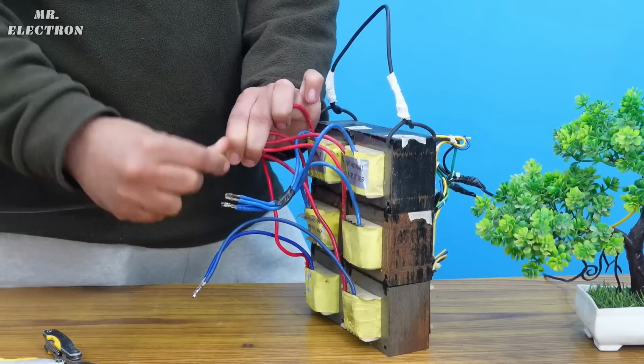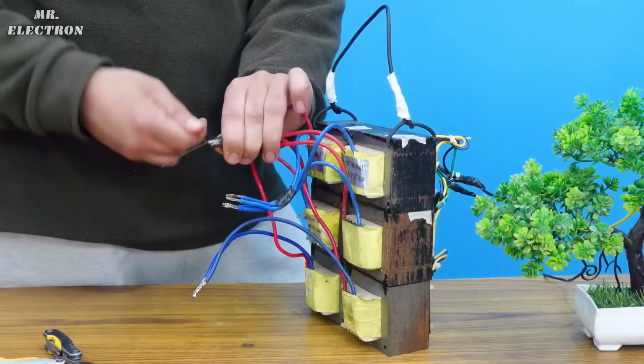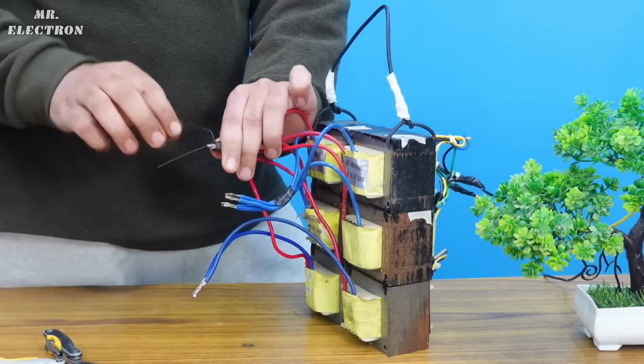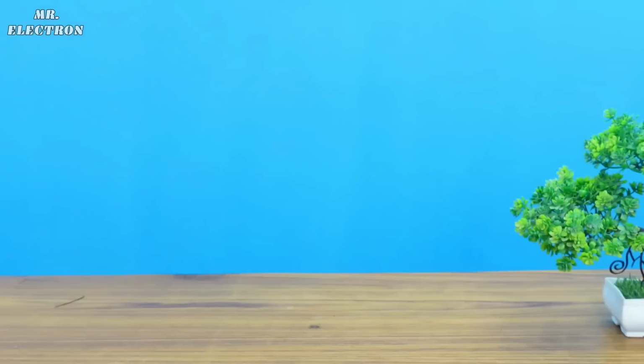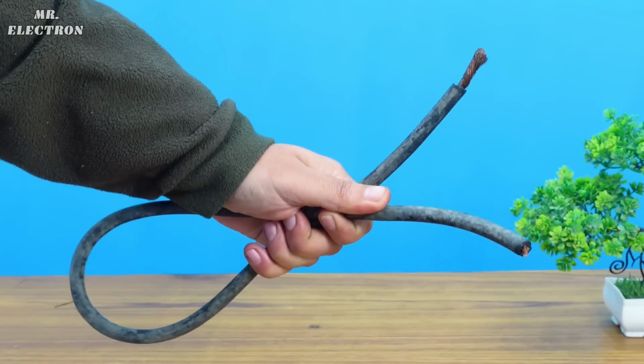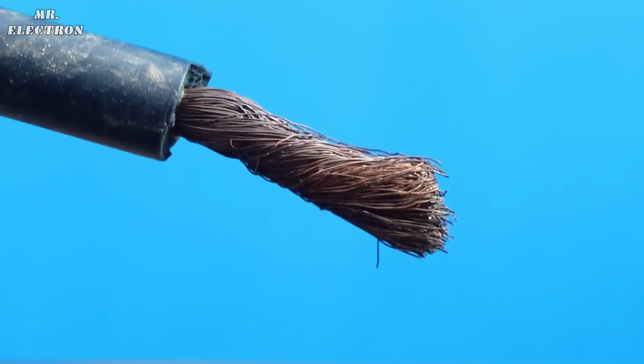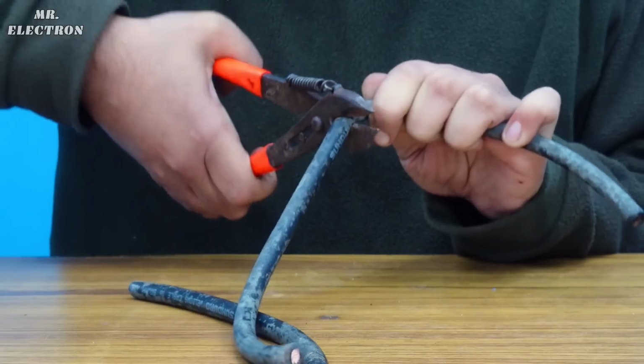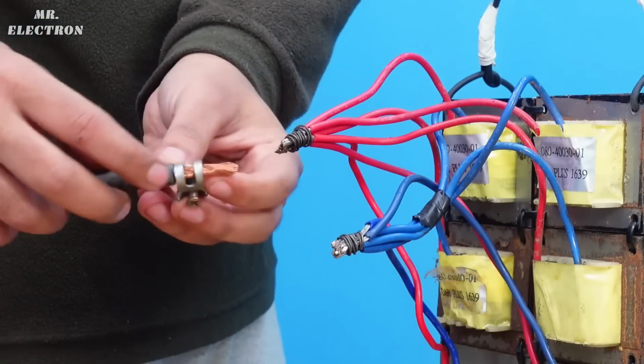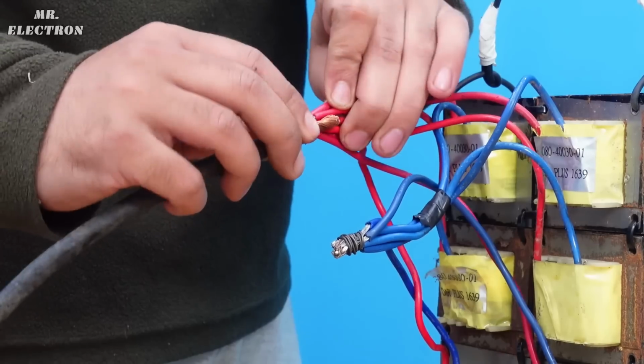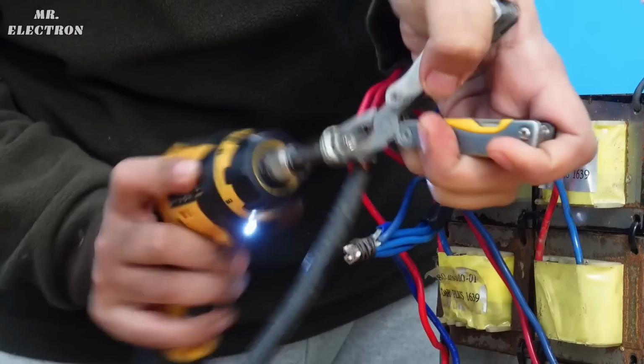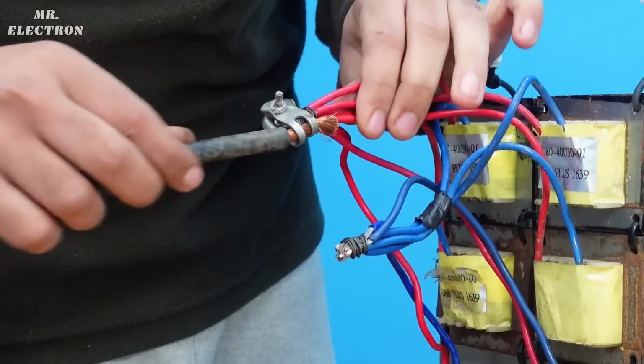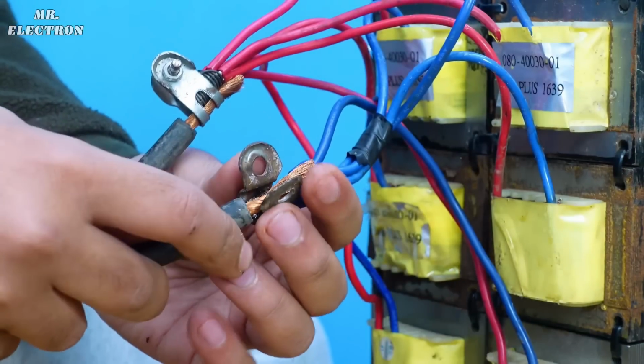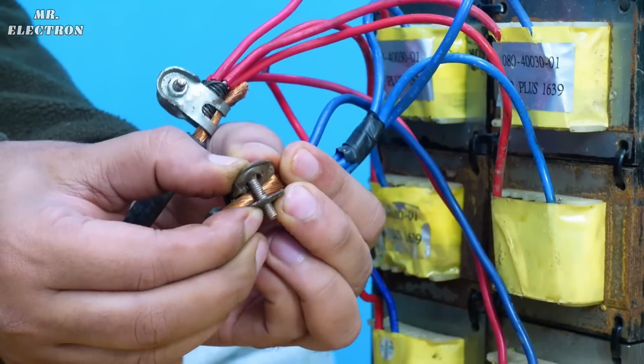Now comes the parallel connection of the output wires, for which I'm using this iron string used in building constructions. There is no specific reason for using them besides bundling. Next, I will use this discarded welding cable that can handle up to 150 amperes. Now, it's extremely important to use a high current copper wire to minimize the voltage drop. Here you can see the way I'm connecting the welding cables to prevent any heat loss that could occur through connectors.